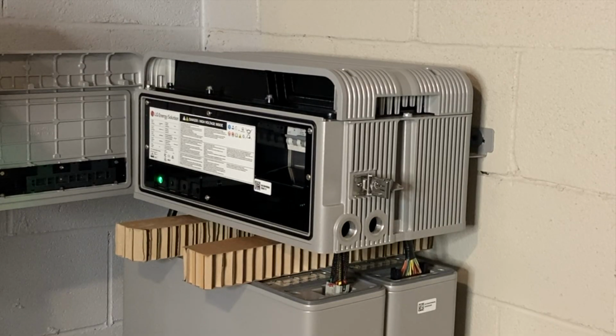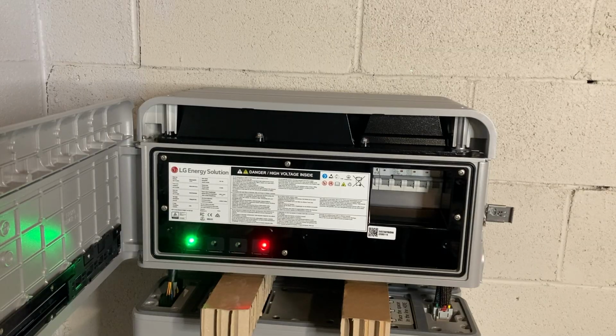Now we'll go ahead and start removing these spacers and connecting the BMS to the batteries themselves. And there's that blinking fault light it was referring to, so it looks like we're all good here. We're going to turn off the circuit breaker, get this closed up, and remove the spacers.